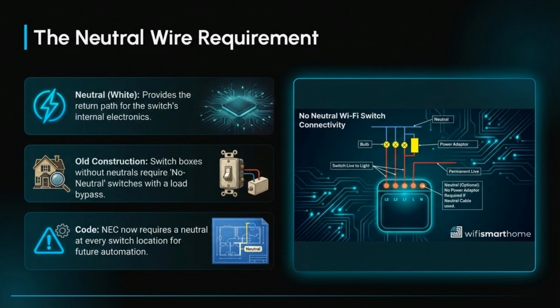A critical requirement is the neutral wire, providing the return path for the switch's internal electronics. NEC now requires a neutral at every switch location for future automation.